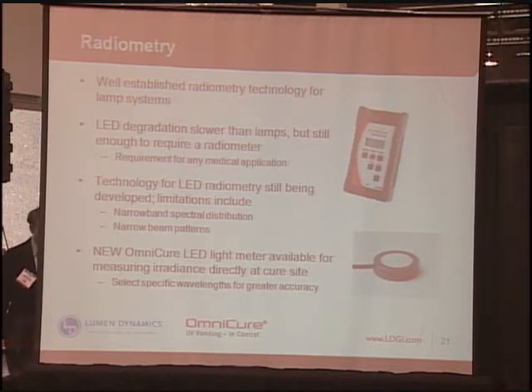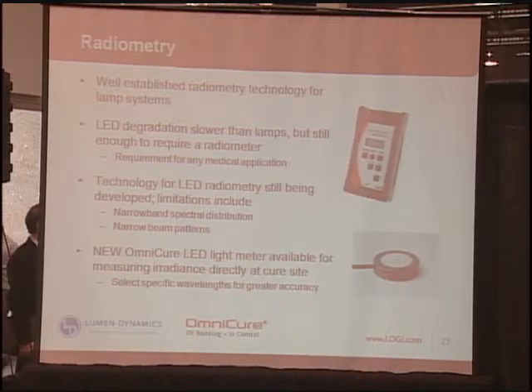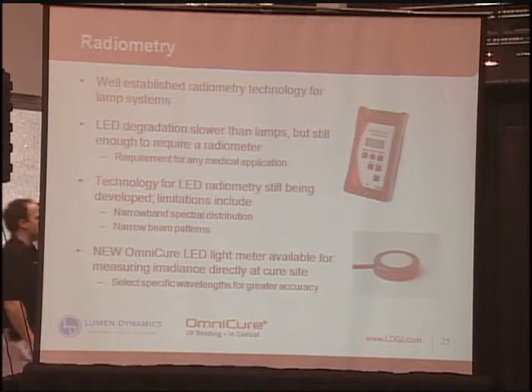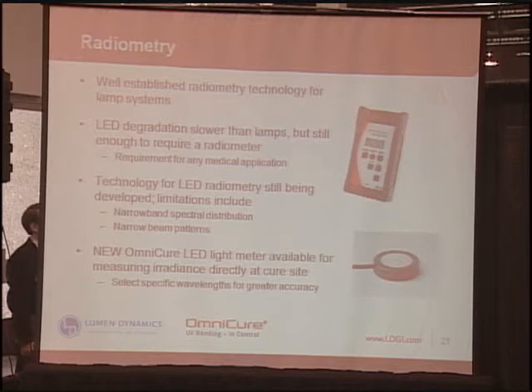So we've actually introduced the new Omnicure LED light meter, which we think has really tackled both of these challenges in a very unique product. What we've done is we have a very special calibration process where we actually calibrate the sensor at 10 nanometer intervals from 300 nanometers up to 720 nanometers. What this allows you to do is you can actually now select the specific wavelength that you're using to match up with your LED system and measure the output at that specific wavelength, knowing that your radiometer has been calibrated traceable to NIST at that wavelength. So we think it's a pretty unique product that, again, will be very helpful for medical device manufacturers who need radiometry to measure and maintain the output for their systems.